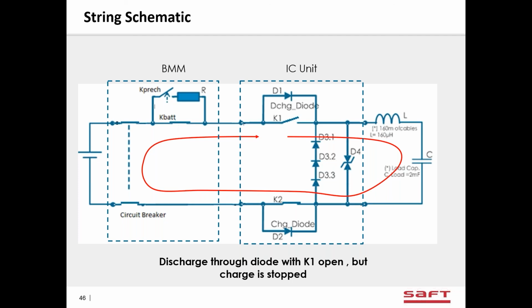That means to bring it back on, somebody has to go and physically reset the breaker back on. If it's a smaller system, we can handle the current, we can do it with K2, and then the battery can automatically charge back up through the diode D2, and nobody would have to go there to reset any breakers. So on smaller systems, we can add the extra feature to make it more autonomous, with less interaction with a human.